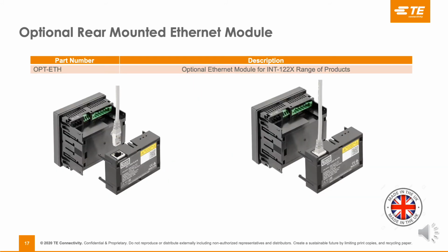The Integra 1221 and 1222, as we mentioned, come with Modbus and pulsed output as standard. However, we have designed a module for the back of the products, which is an Ethernet module, part number OPT-ETH. It simply clips onto the back of the unit, you configure it, and then you drop the RJ45 cable in place.